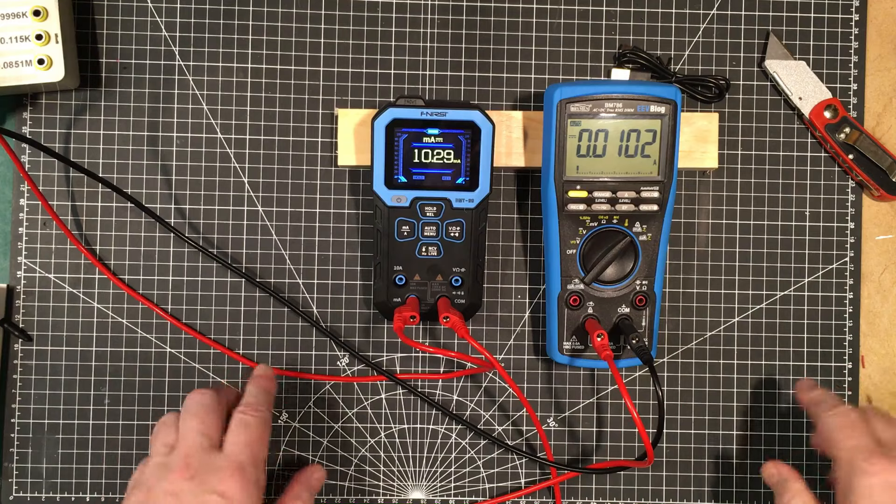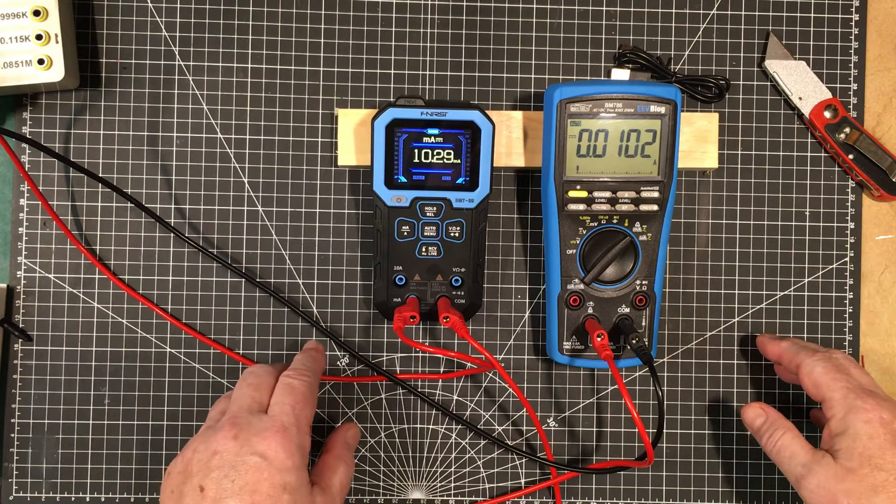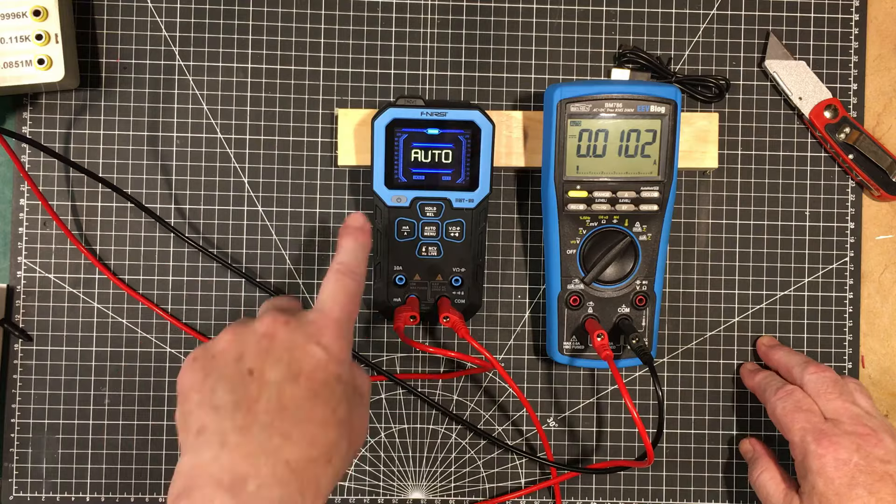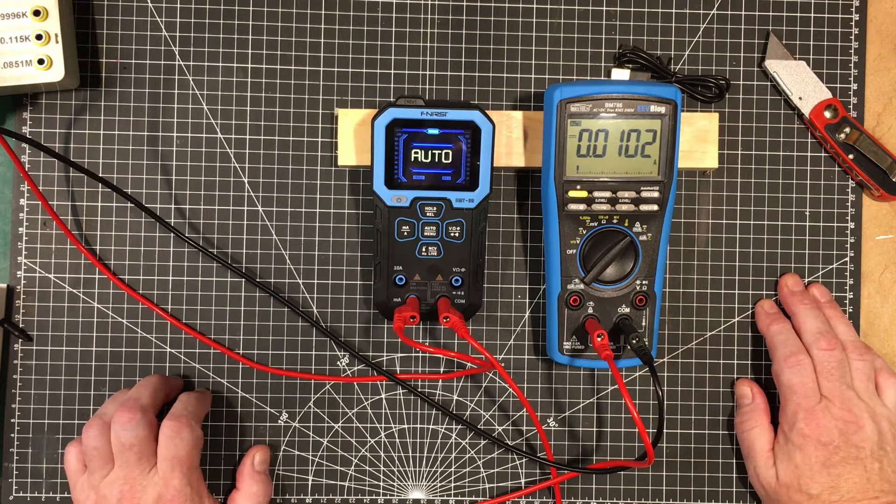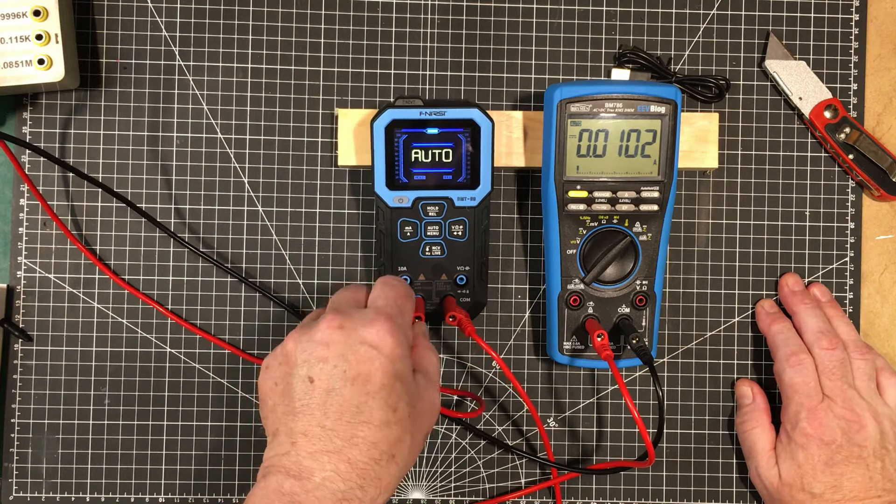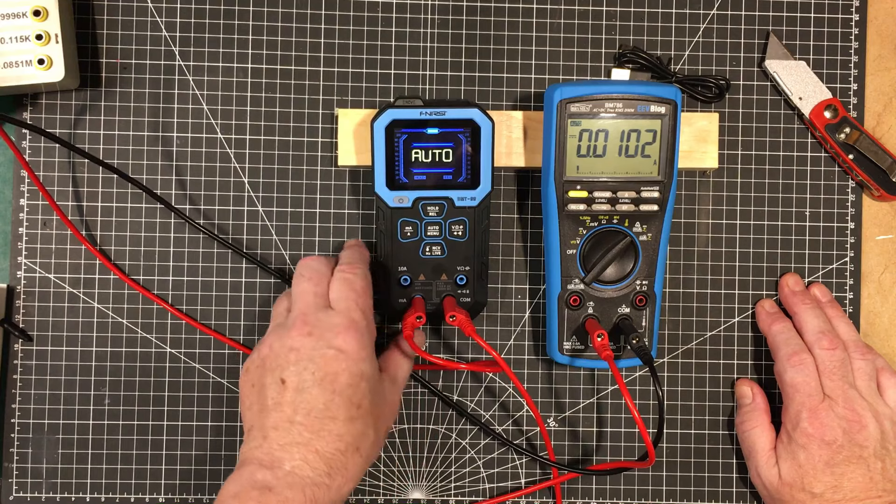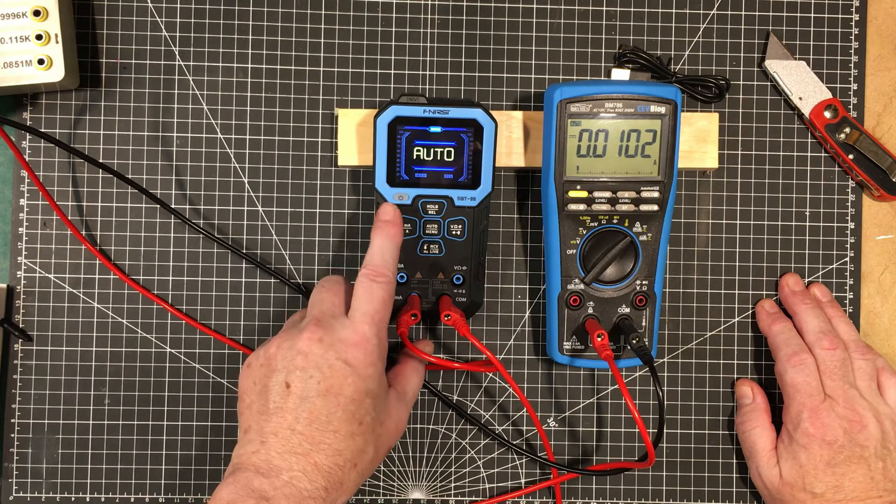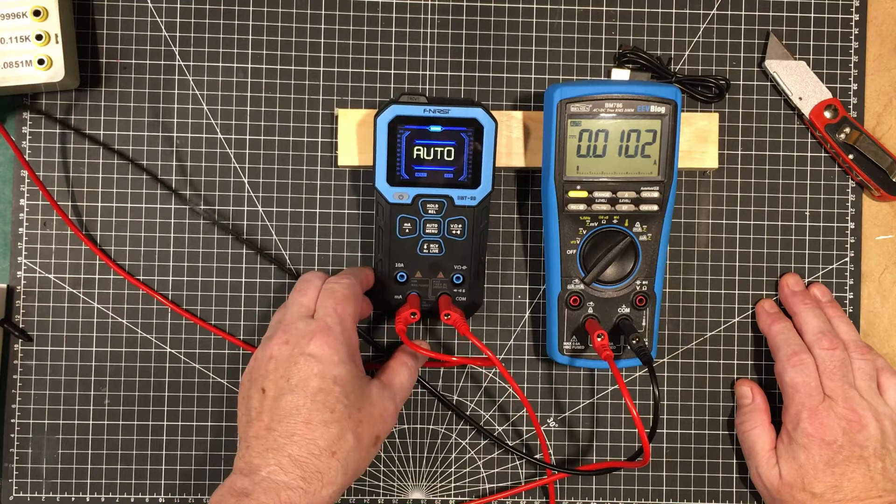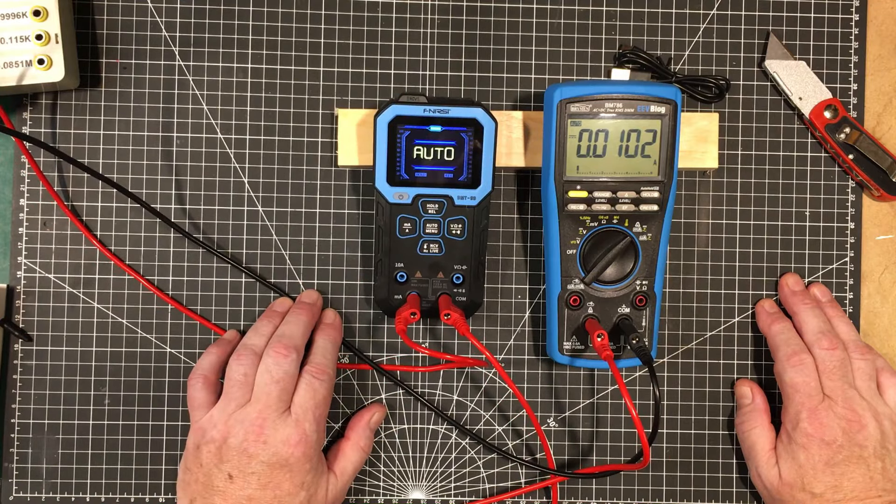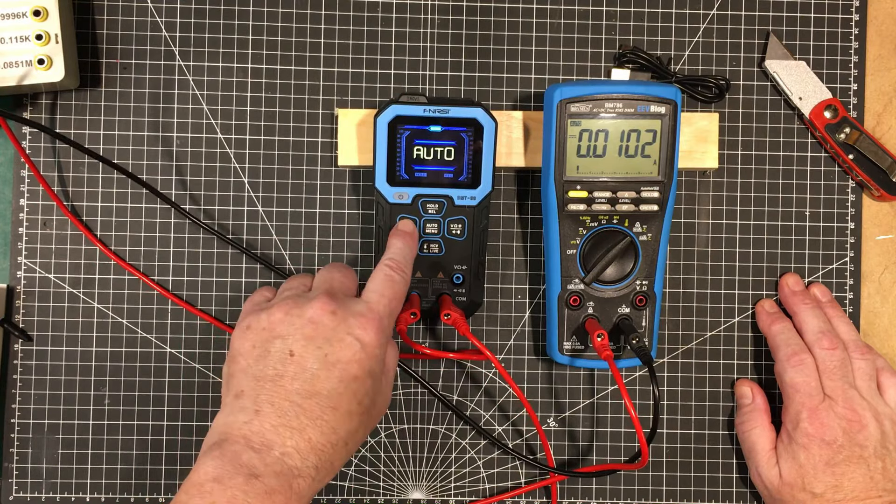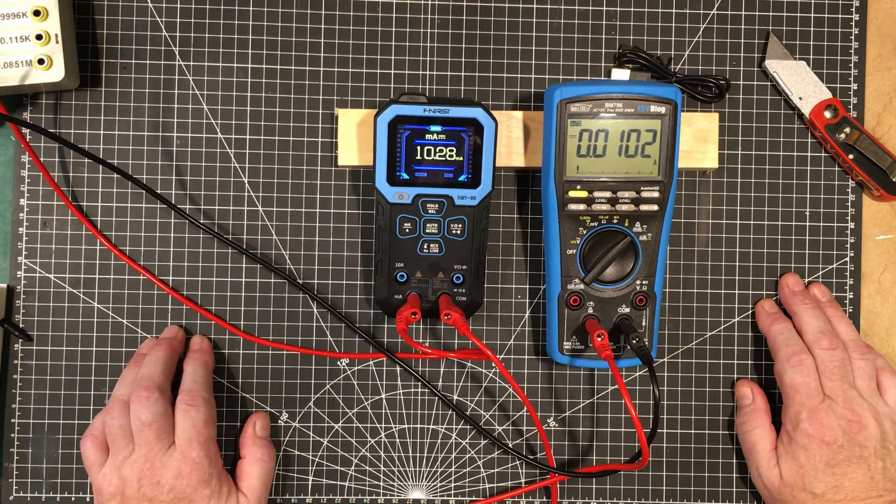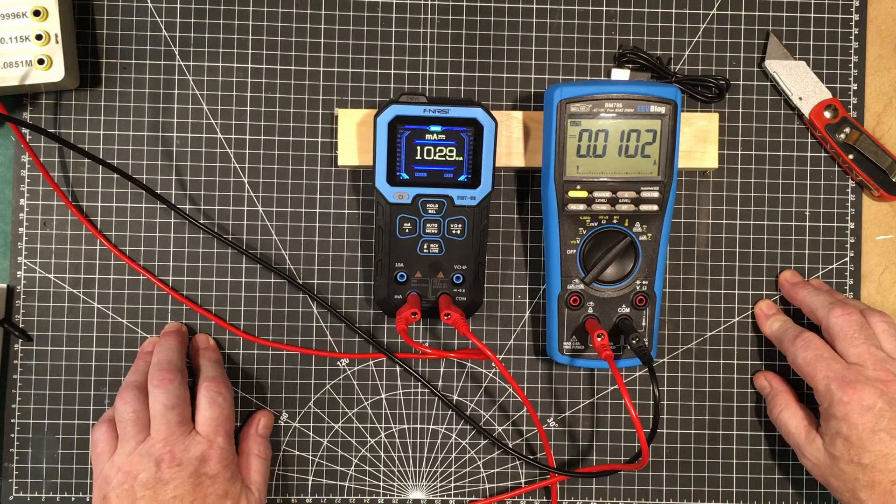So it's not able to auto. So if I go into auto mode, it doesn't detect current automatically, even though the inputs are different for current. So you'd think it would, but it doesn't. So in current mode, you have to select the mode first. So we'll select that and we're in milliamp mode. And there we are at 10.29 milliamps.